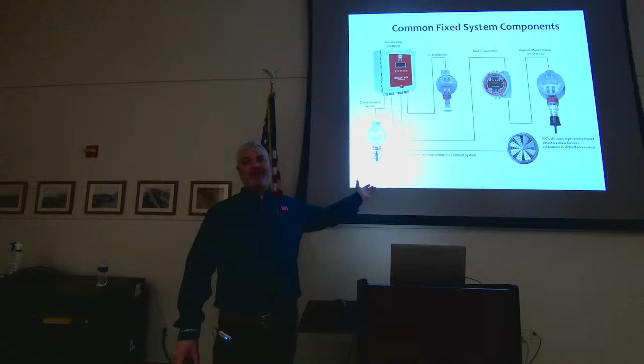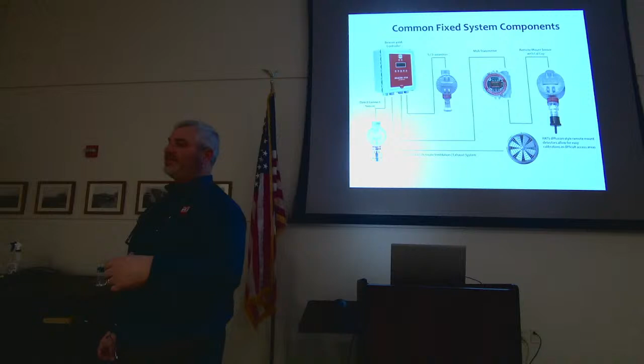They're going to look at that application and say, all right, we're going to make this easy. So what doesn't happen when you design your new plants? Well, usually the engineers will copy and paste what's called a master spec, and they'll say, oh, I need gas detection in this room. Click, drag, paste. How often do those work out for you? Not very often, right? Because it usually says, oh, we need a gas monitor in here. Okay, what type of gas monitor? You're going to have to direct whoever installs that equipment in your facility. You're going to have to tell them what you want, and it has to meet your needs.